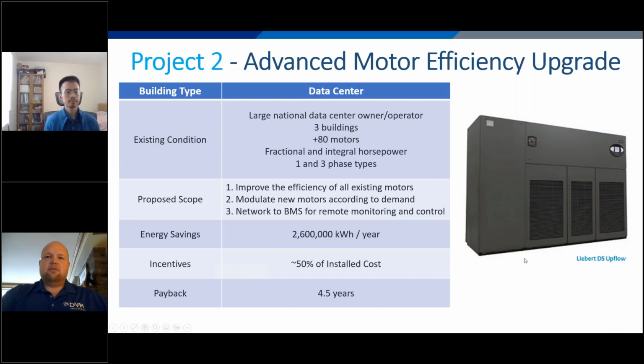Then going the next step of modulating those new motors according to demand. So adding VFDs where appropriate and coupling those VFDs to some sort of input device that's going to actively modulate that motor. And for the single phase applications, similar dynamic there, modulating those motors whenever possible to take advantage of those affinity law dynamics.